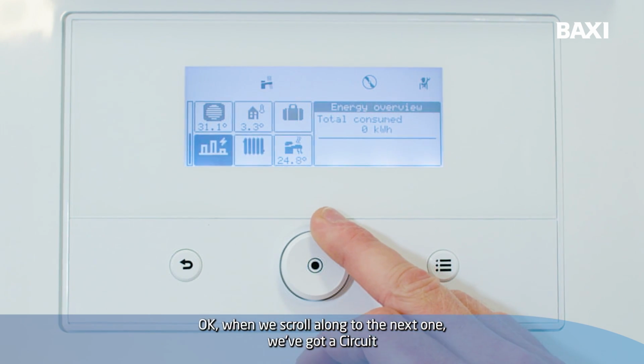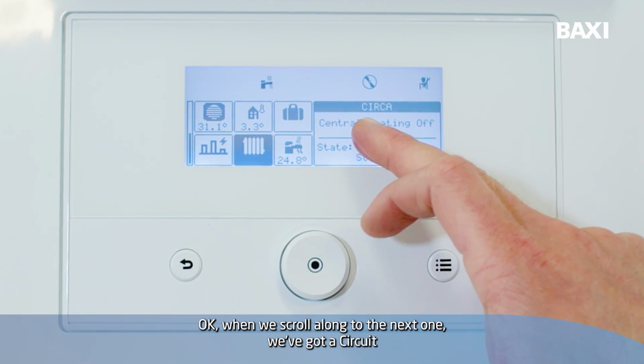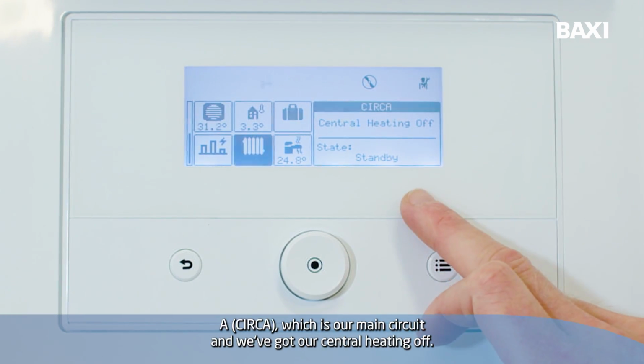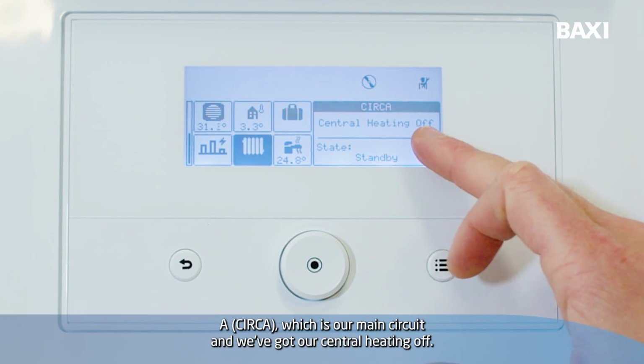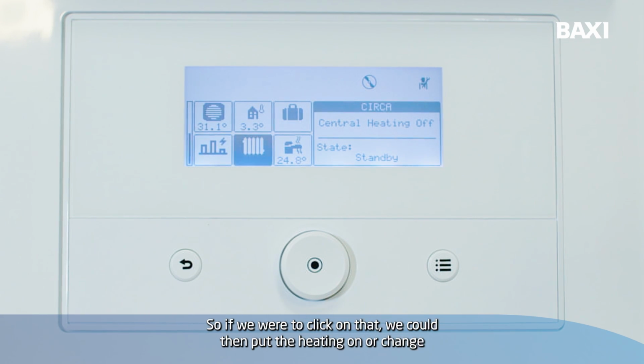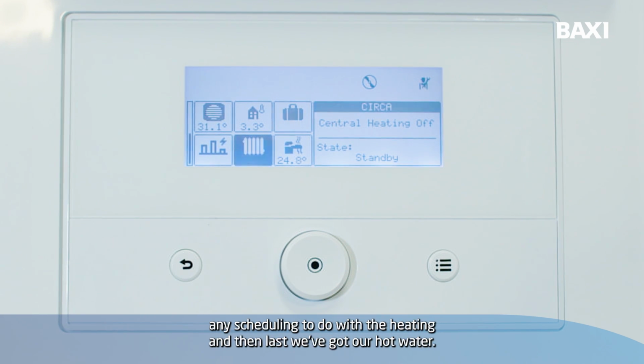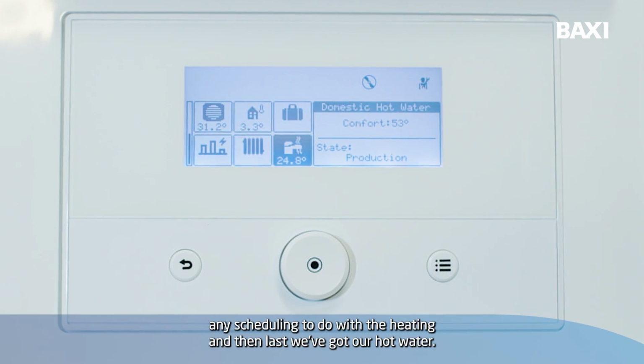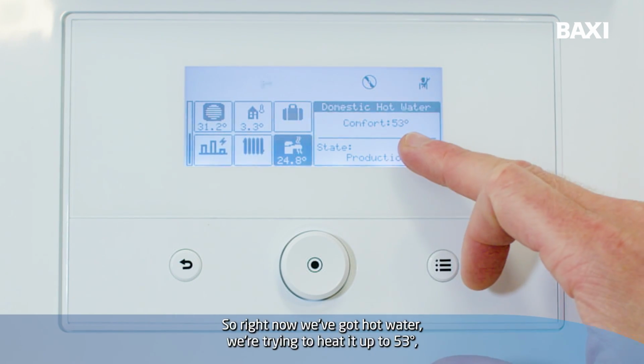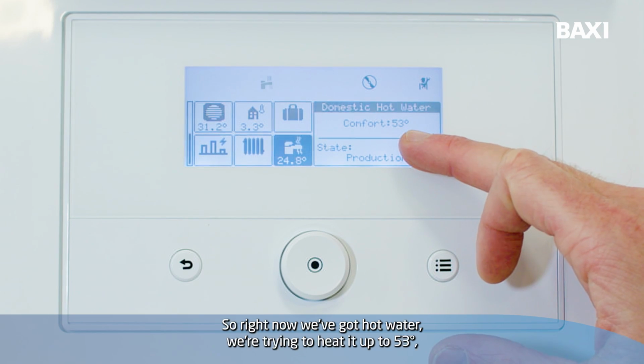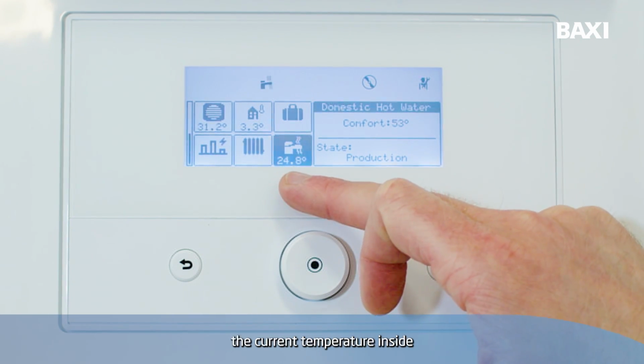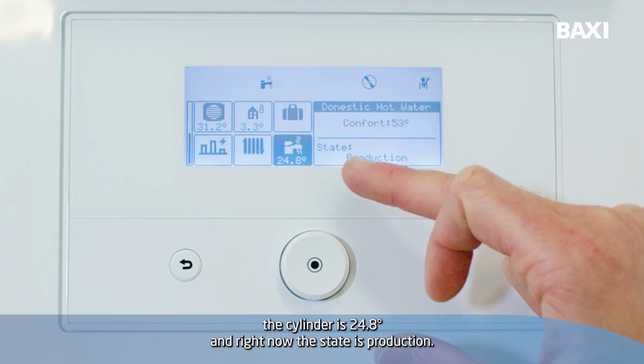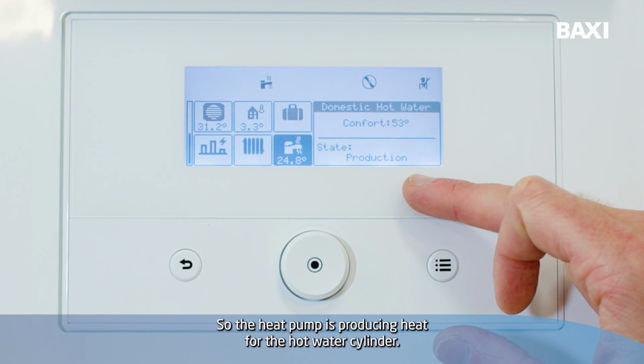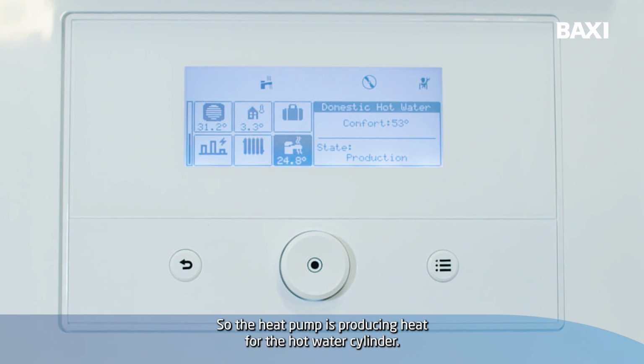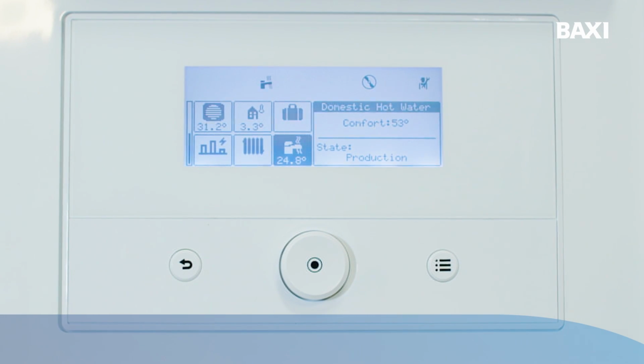When we scroll along to the next one, we've got our circuit A, which is our main circuit, and we've got our central heating off. If we were to click on that, we could then put the heating on or change any scheduling to do with the heating. And then last, we've got our hot water. Right now, we're trying to heat it up to 53 degrees. The current temperature inside the cylinder is 24.8. And right now the state is production. So the heat pump is producing heat for the hot water cylinder.